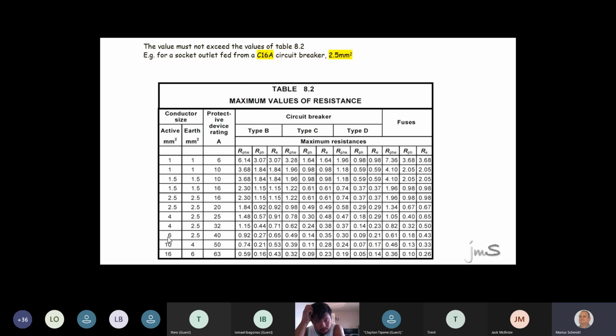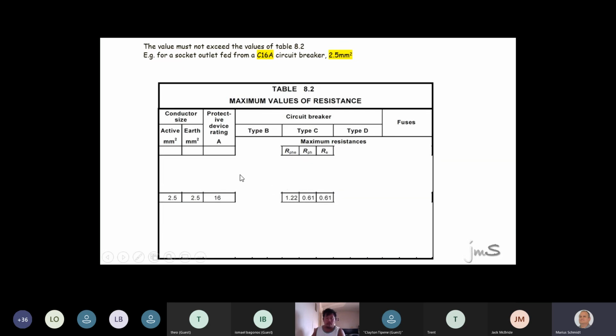Your earth is based on the active conductor. We're not teaching regs tonight, but there's a table called 5.1. It tells you what the active conductor is, what the earth must be. There's also a formula where you can work out what the earth resistance size will be. Right, guys, so just to continue, you all agree on this picture, it's a C16 amp breaker. The resistance of the earth is 0.61. The ohm reading cannot be more than 0.61 of an ohm. Are you okay with that?